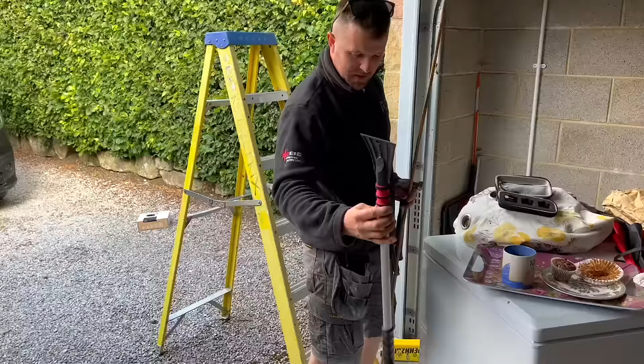Finally, remind customers that these cables live in a hostile environment. There's water, for a start, mud, road grit, foxes, rodents. They should remove the lead after charging whenever possible and inspect it before every use. The IET says to remember that a cable gully isn't just a bit of civil engineering. Treat it like any other EV installation. Check the permissions, assess the earthing, size the cable properly, and don't rely on an OPDD to solve problems it wasn't designed to fix. I'll pop a link to the full advisory in the show notes.